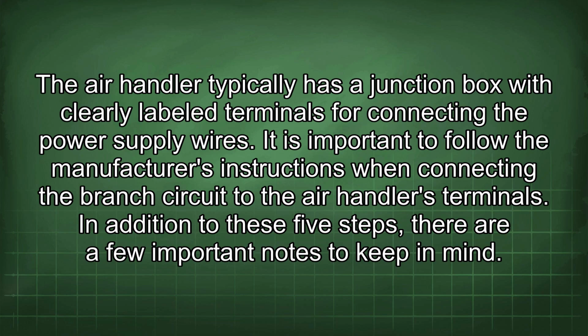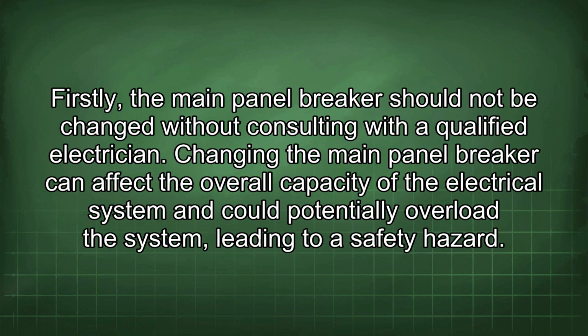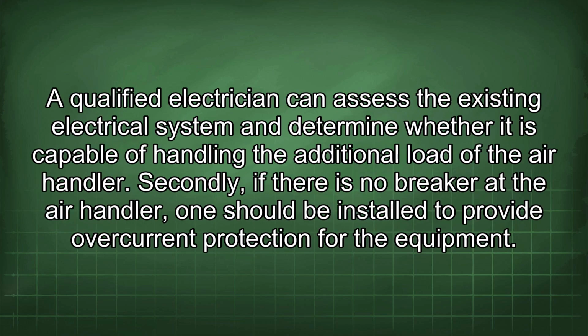In addition to these 5 steps, there are a few important notes to keep in mind. Firstly, the main panel breaker should not be changed without consulting with a qualified electrician. Changing the main panel breaker can affect the overall capacity of the electrical system and could potentially overload the system, leading to a safety hazard. A qualified electrician can assess the existing electrical system and determine whether it is capable of handling the additional load of the air handler. Secondly, if there is no breaker at the air handler, one should be installed to provide overcurrent protection for the equipment.